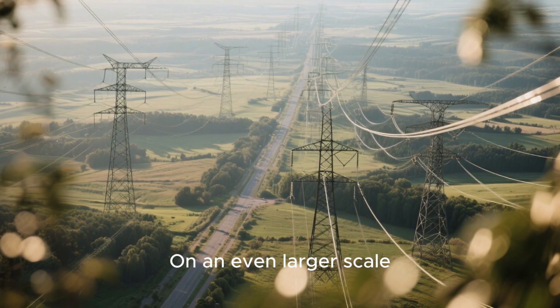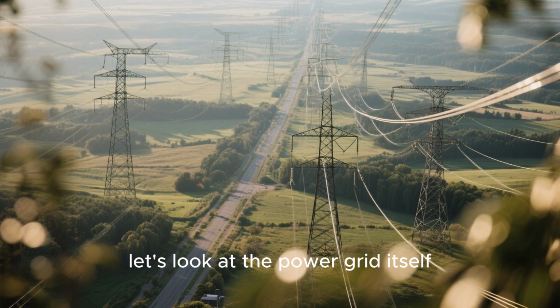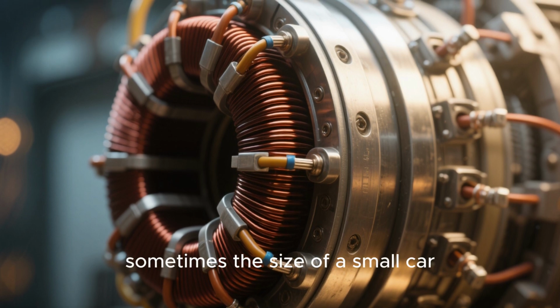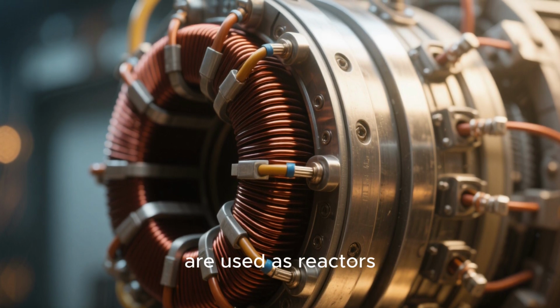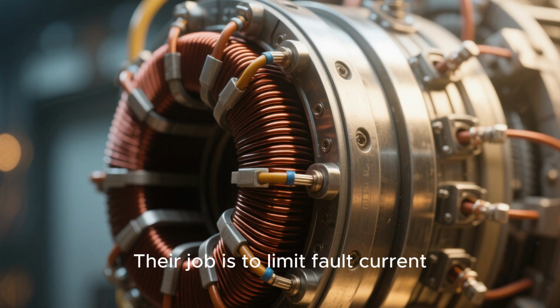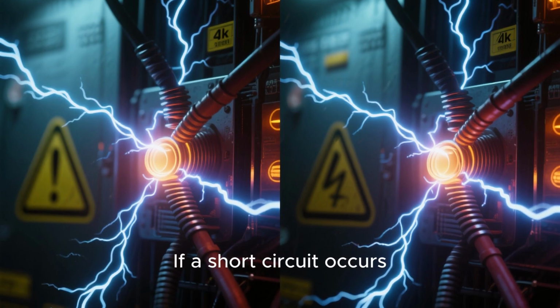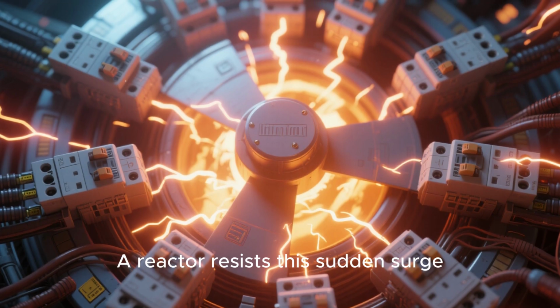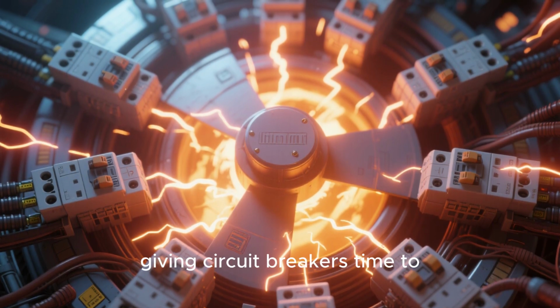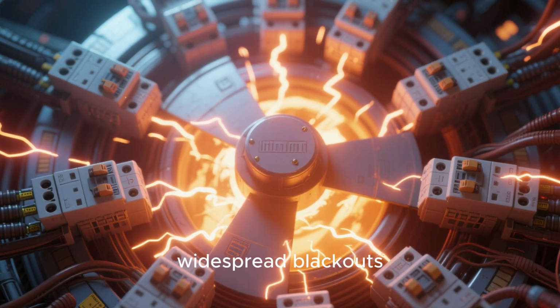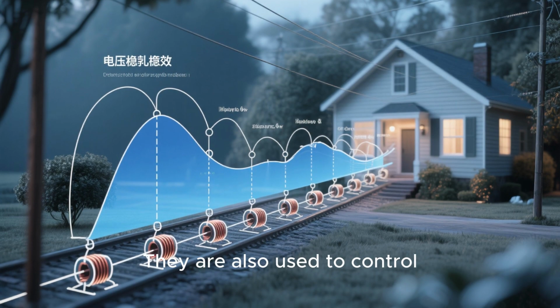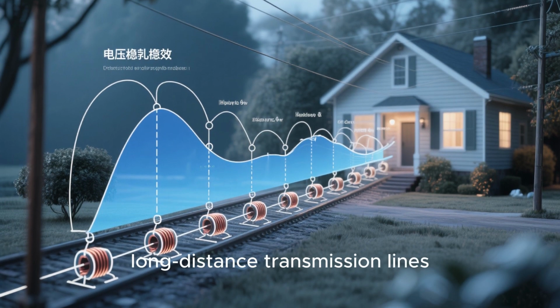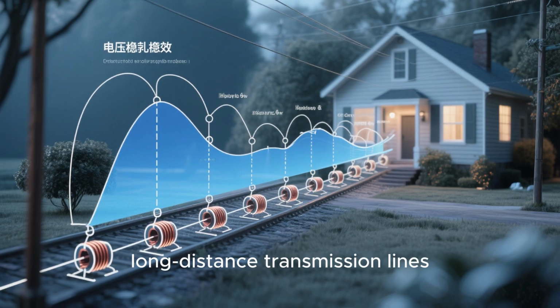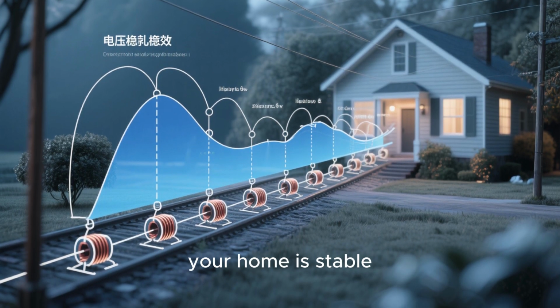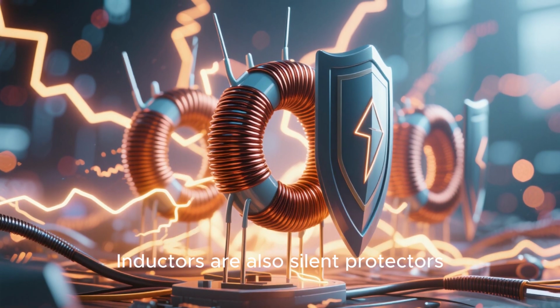On an even larger scale, let's look at the power grid itself. Huge inductors, sometimes the size of a small car, are used as reactors. Their job is to limit fault current. If a short circuit occurs, the current can surge to catastrophic levels. A reactor resists this sudden surge, giving circuit breakers time to operate and preventing widespread blackouts. They are also used to control voltage and stabilize long-distance transmission lines, ensuring the power that reaches your home is stable.